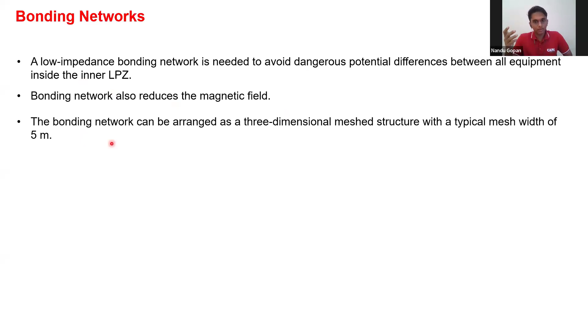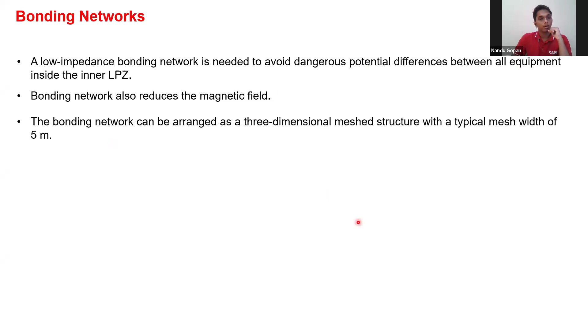Basically, if you have RCC steel, you can put some superimposed conductors, and you can use that RCC steel for bonding network purposes. You can put an earth point nearby, and very efficiently you can control this potential difference. Now, where is all this bonding required? You are supposed to connect all the metal components coming inside the building from one zone to another zone. If there are metal facades or metal frames or elevator rails or cranes coming from zone 1 to zone 2, you are supposed to bond them thoroughly.